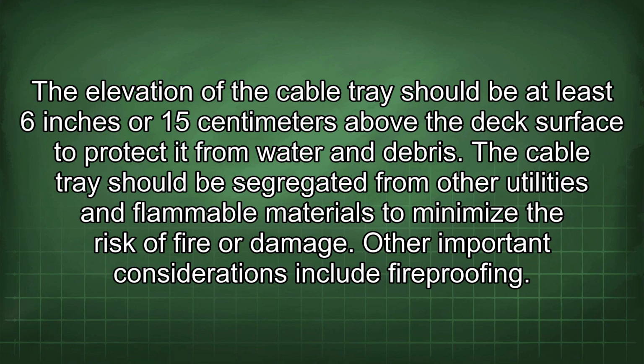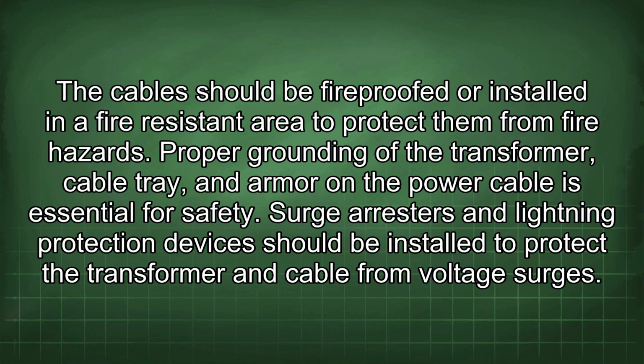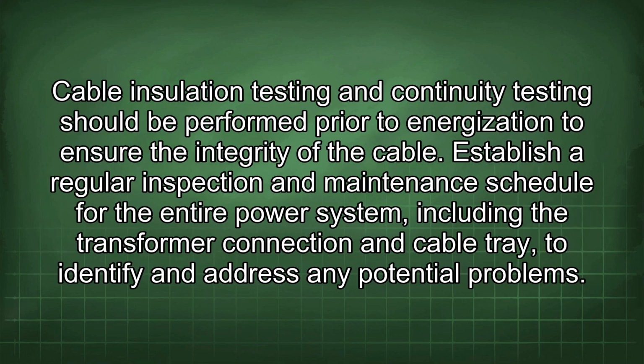Other important considerations include fireproofing. The cable should be fireproofed or installed in a fire-resistant area to protect it from fire hazards. Proper grounding of the transformer, cable tray, and armor on the power cable is essential for safety. Surge arresters and lightning protection devices should be installed to protect the transformer and cable from voltage surges. Cable insulation testing and continuity testing should be performed prior to energization to ensure the integrity of the cable. Establish a regular inspection and maintenance schedule for the entire power system, including the transformer connection and cable tray, to identify and address any potential problems.